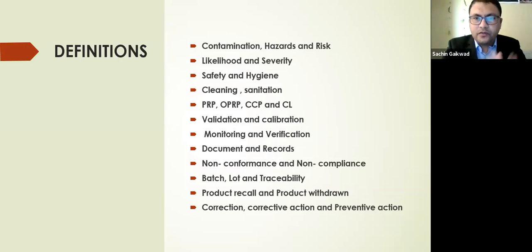So validation, you decide the parameters here. You validate the parameter, meaning whether that particular process step, during operation, is acquiring that particular result or not. For that I need calibrated equipment.